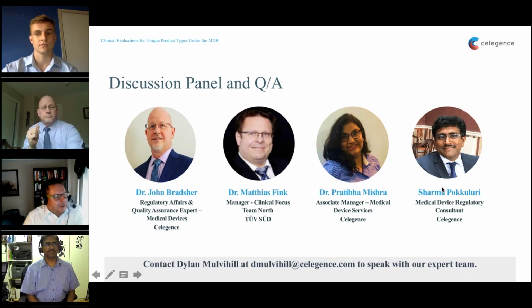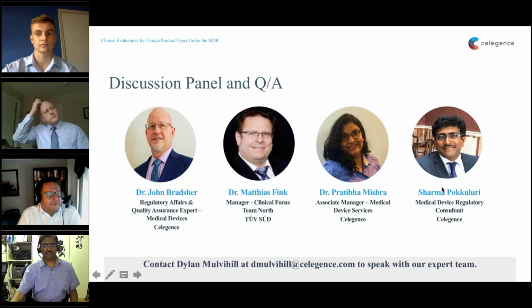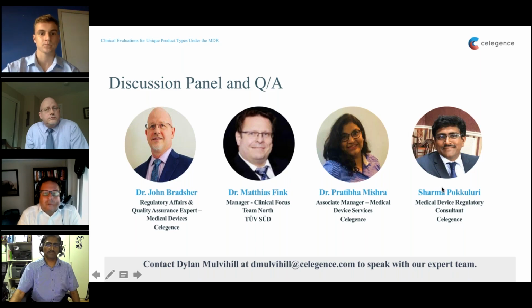It depends. You have to differentiate a little bit here between pre-market and post-market investigations. Of course, if you have a device already marketed outside of the European Union and you conduct a post-market study there, you might be able to use this for the initial CE mark in Europe. Then, if you're planning to do a new study, always take into consideration the requirements of Annex 15 of the MDR. But this goes without saying: every clinical study, regardless of what part of the world it's conducted in, should follow ethical and scientific standards. So GCP or ISO 14155 should always be considered.